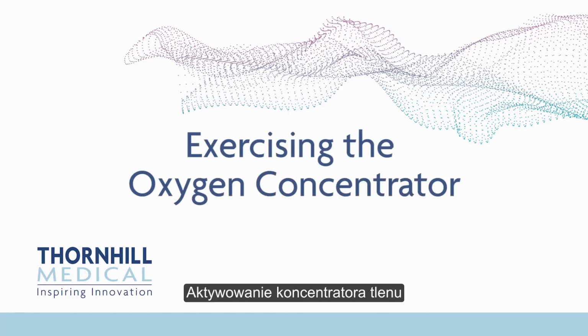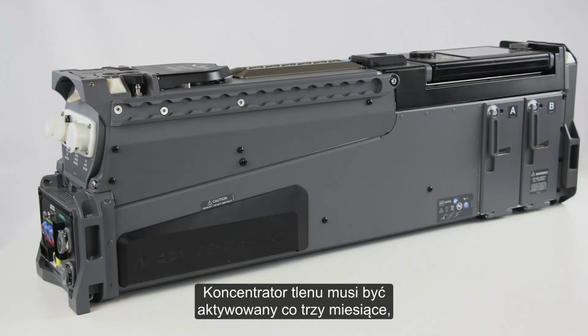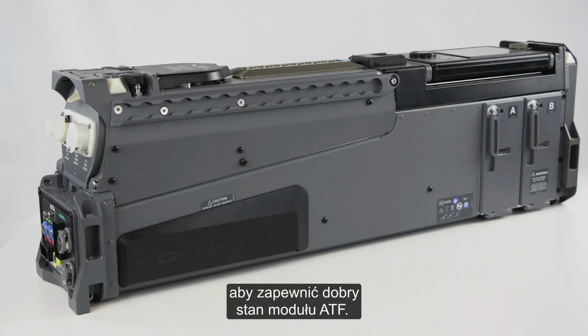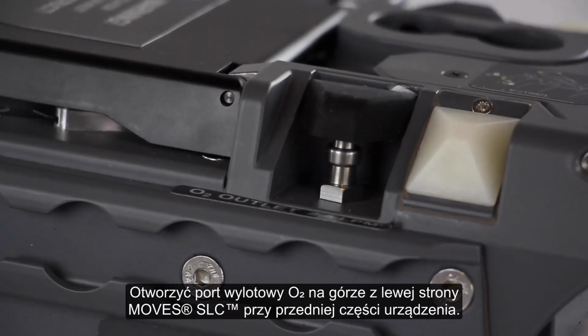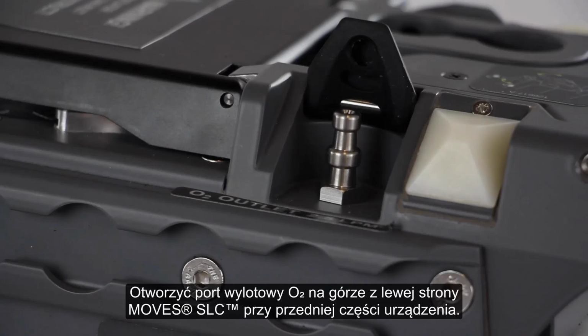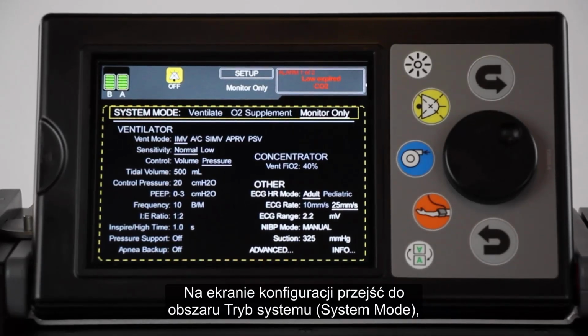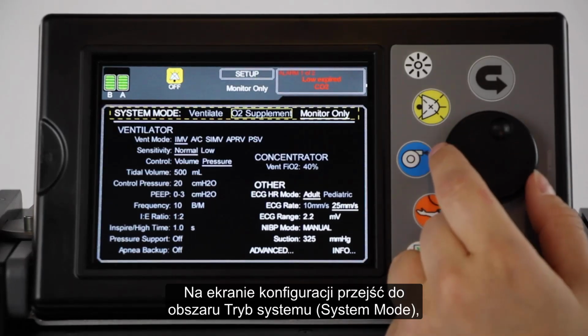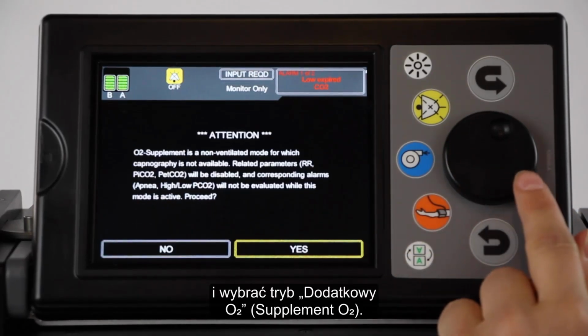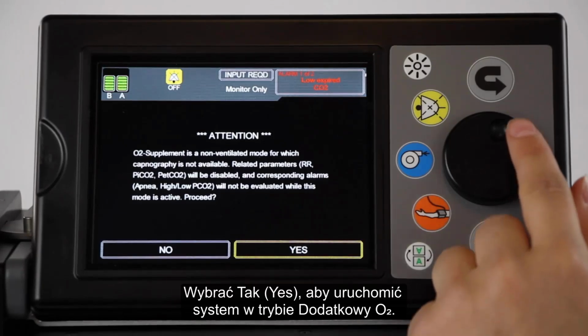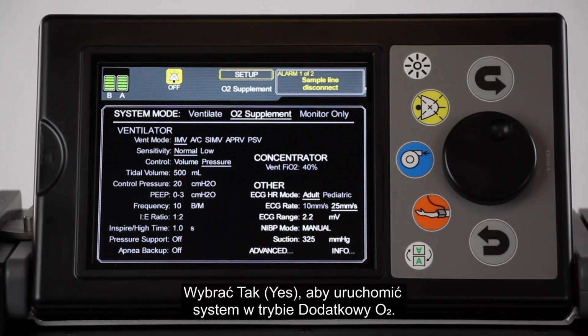Exercising the oxygen concentrator. The oxygen concentrator must be exercised every 3 months to ensure that the ATF module does not degrade. Open the O2 outlet port on the top left of Moves SLC, near the front of the device. On the setup screen, navigate to the System Mode area and set the mode to O2 Supplement. Select Yes to start the system running in O2 Supplement mode.